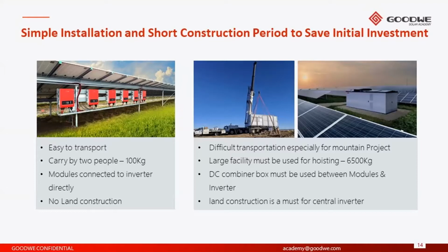the inverter itself. With string inverters, you also don't need to install the DC combiner box, because essentially the string inverters contain many MPPTs, and as I'll take you through the slides, you'll see how many MPPTs the GoodWe inverters have. By having a large number of MPPTs, it negates the requirement for a DC combiner box, which is necessary when you're installing a centralized inverter. DC combiner boxes mean many DC cables and, of course, a very large DC cable connected from the DC combiner box to the inverter itself. Typically the DC cables are much more expensive than the AC cable, so it leads to a higher BOS cost.